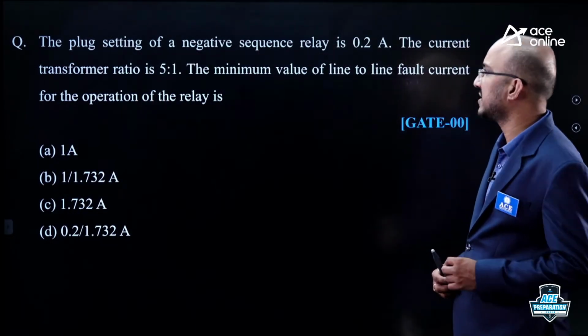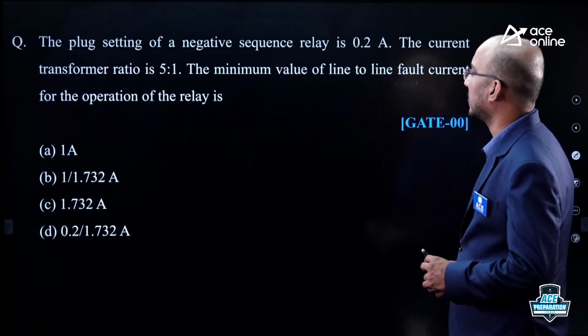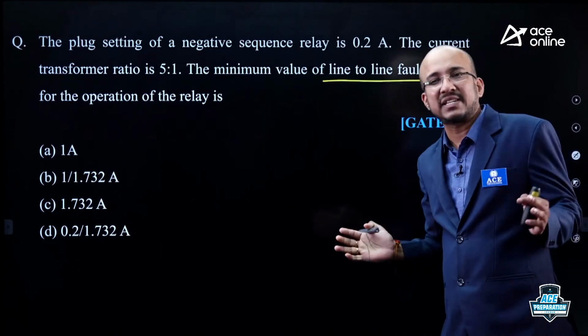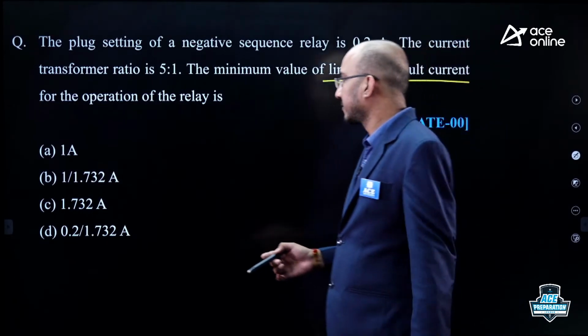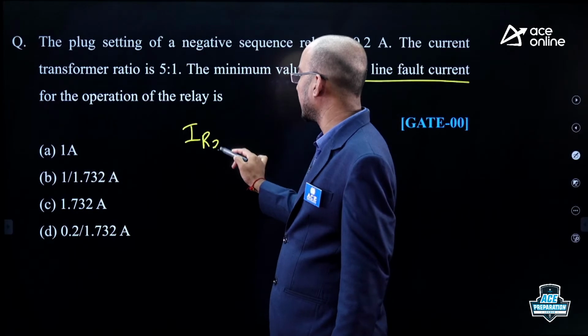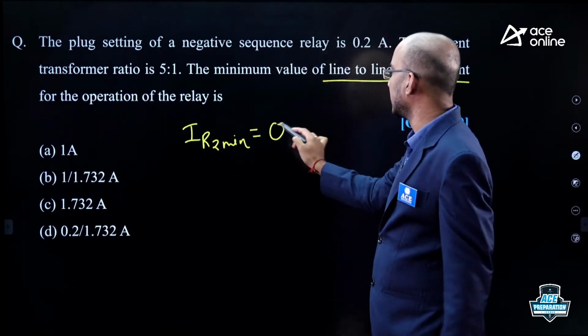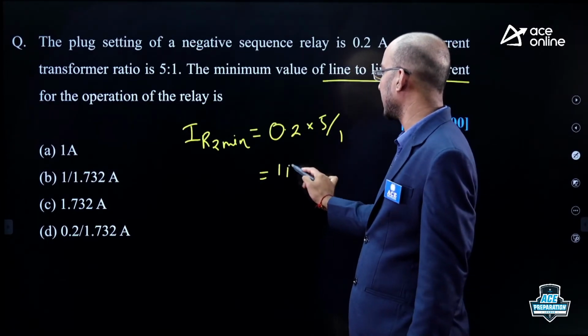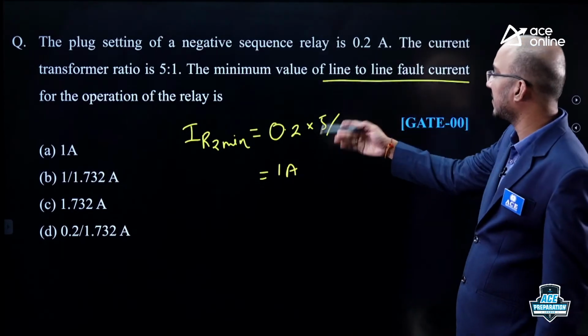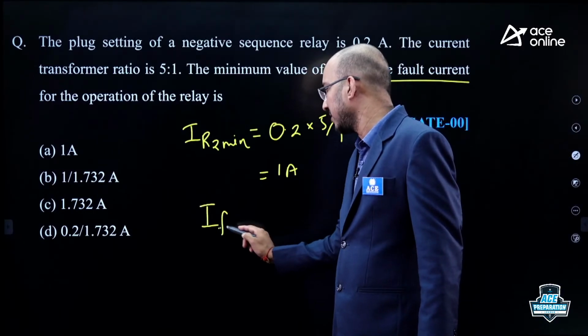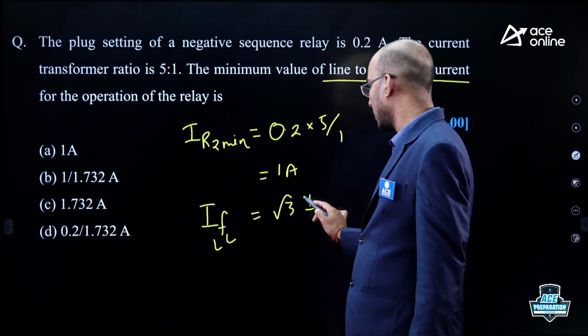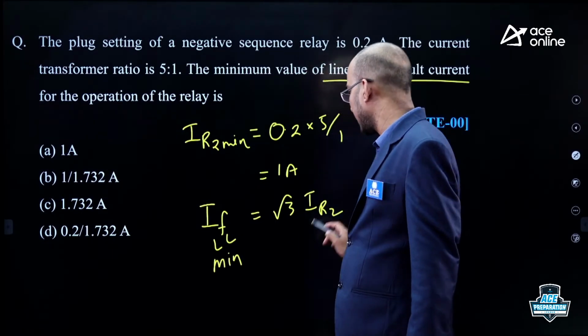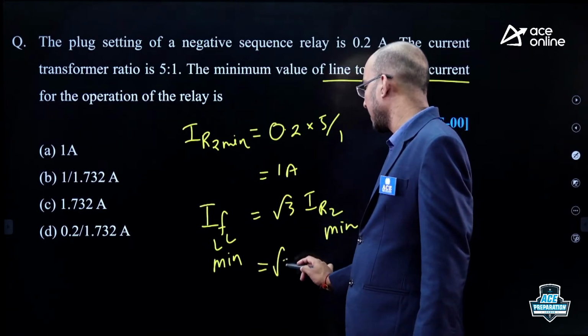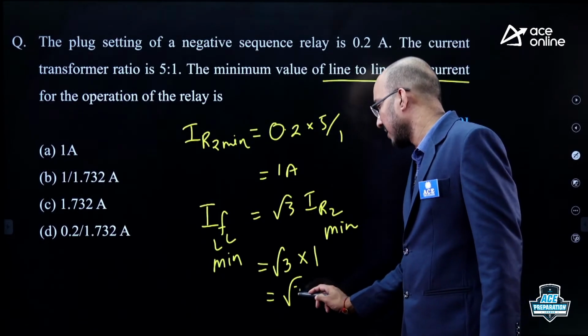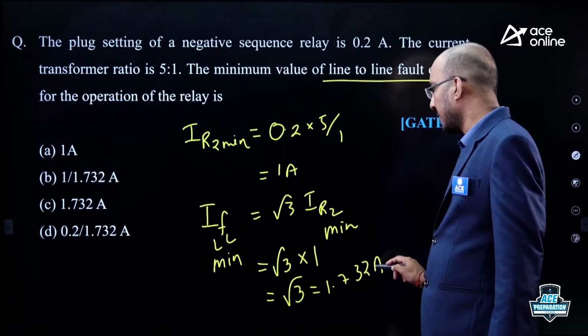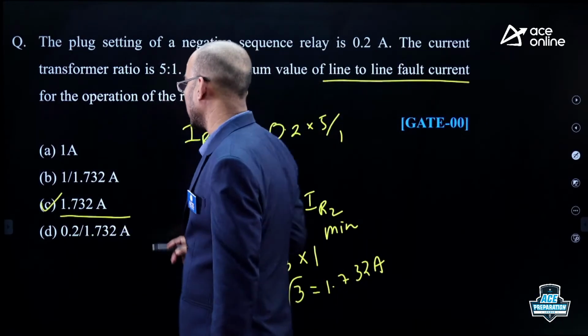Now, let us observe this question. The plug setting of a negative sequence relay is 0.2 amperes. The CT ratio is 5:1. Find the minimum value of line to line fault current. This is the application of fault analysis to the protection subject. Here, the minimum primary side negative sequence current required, IR2, is 0.2 into CT ratio 5/1, which is 1 ampere. But he is not asking for the minimum negative sequence current. He is asking for the minimum value of line to line fault current. For a line to line fault, the current is root 3 times IR2. So, IF minimum is root 3 times IR2 minimum, which is root 3 into 1, that is 1.732 amperes. So, the minimum line to line fault current is 1.732 amperes.